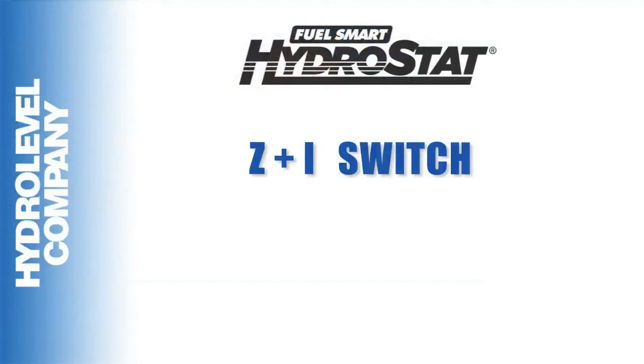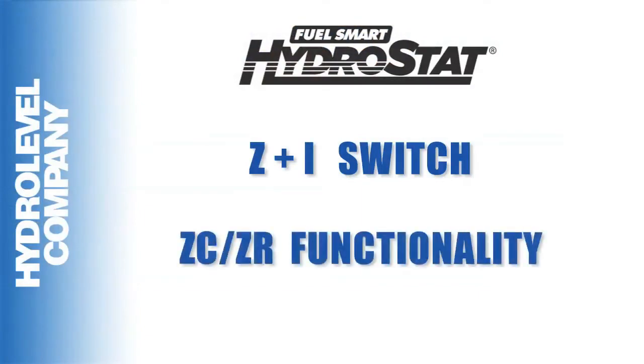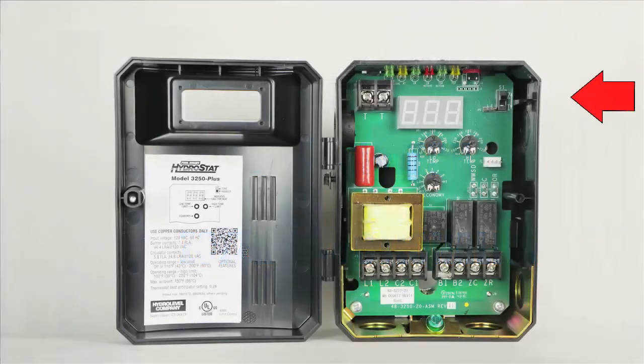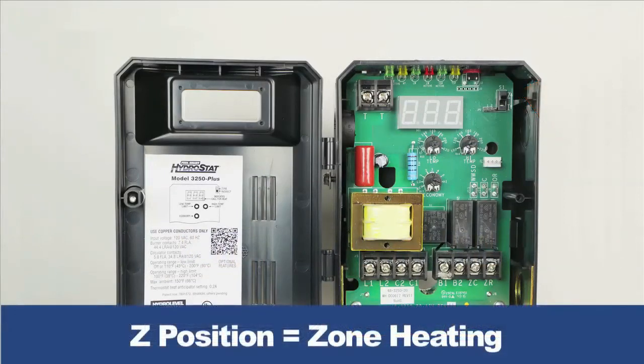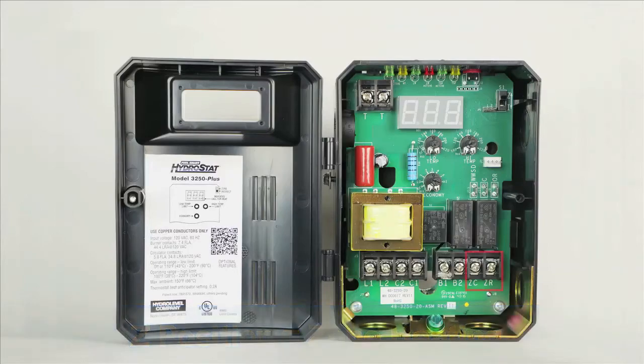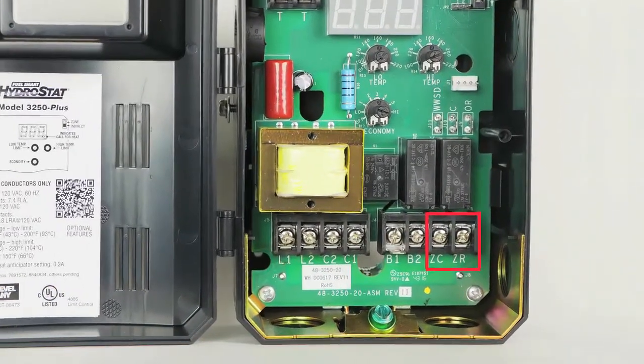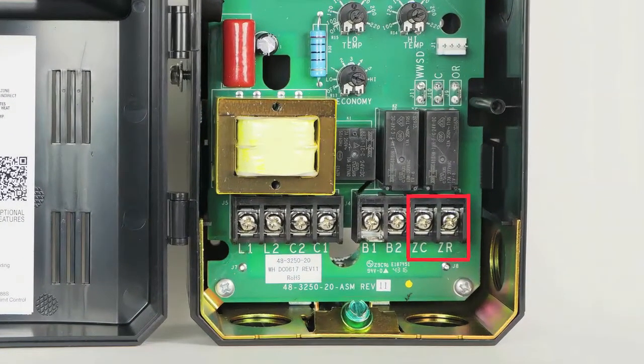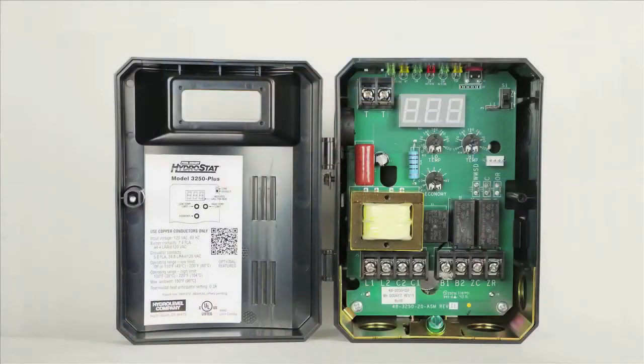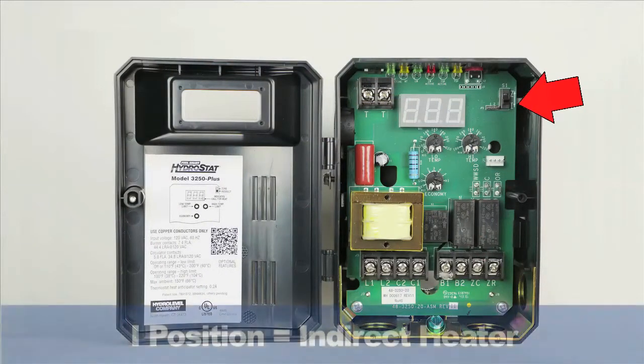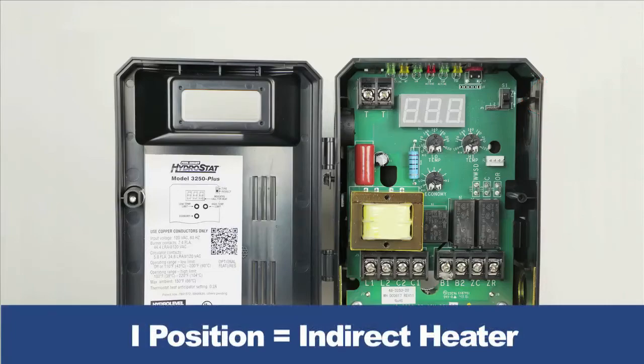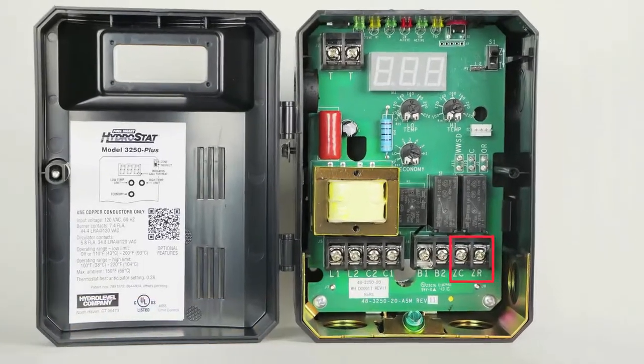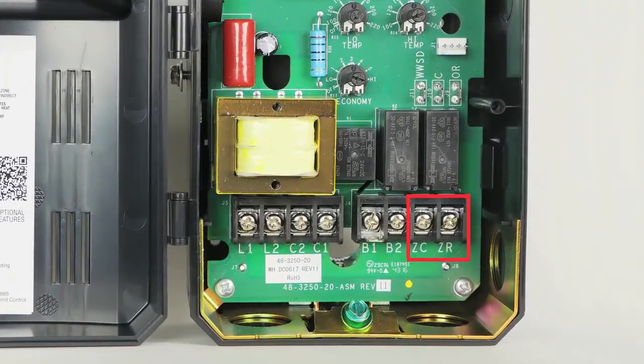Z and I switch with ZC-ZR functionality. When the ZI switch is set to the Z position, which refers to zone heating, the ZC-ZR terminals can be used in a traditional way for controlling external zone relays, especially when a tankless coil is present. When the ZI switch is set to the I position, which refers to indirect heater, the ZR terminal is used to set domestic hot water priority.